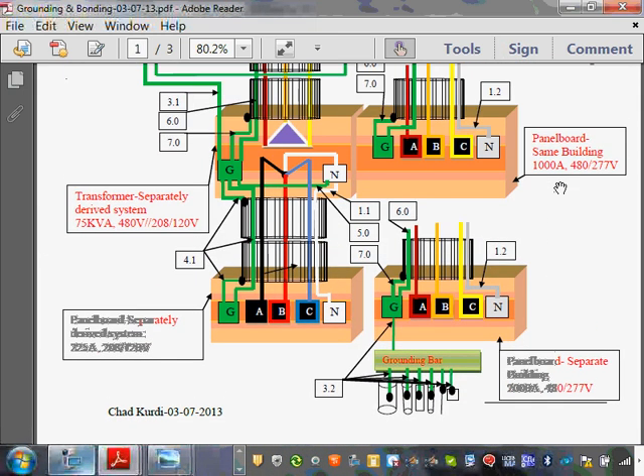Now with your supply side bonding jumper, on the secondary side, you're going to bond the flex that's coming to your building from one side or the other, or both, as you enter. So that conductor, guys, 4.1, could come here, bond the conduits here with a bonding bushing, come inside it. This is a flex, we're using flex. Coming out of here, bond the end, and come all the way back. You only need to bond one side though.